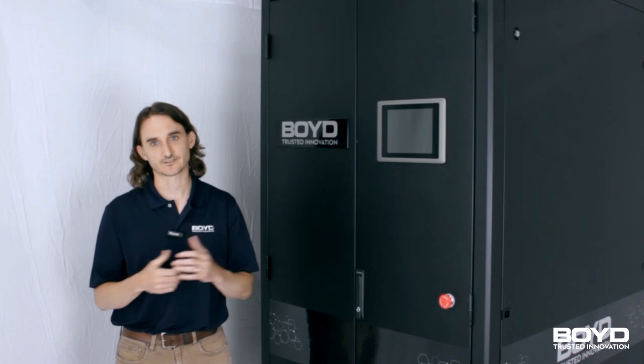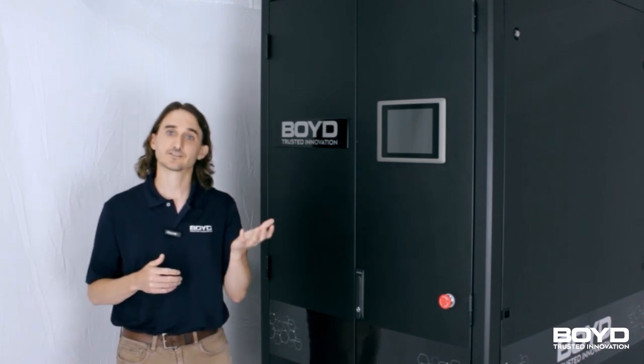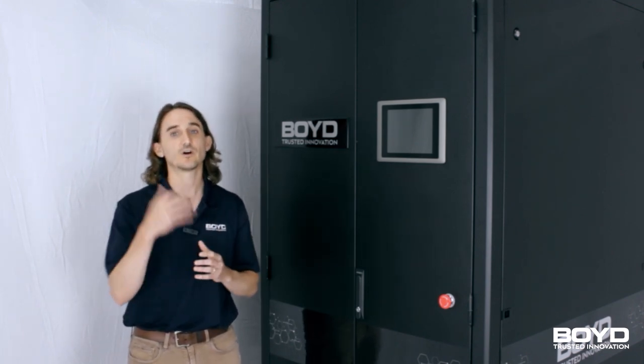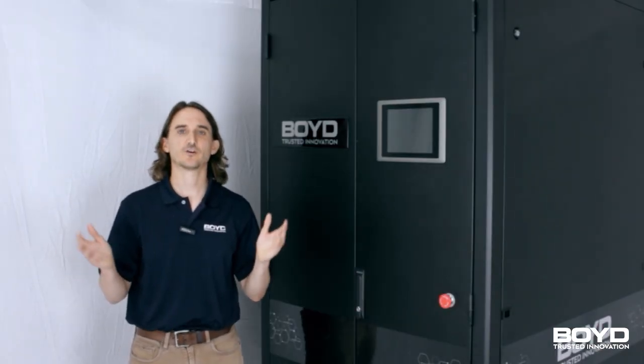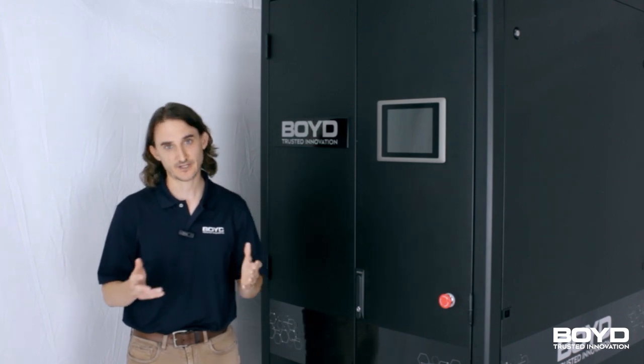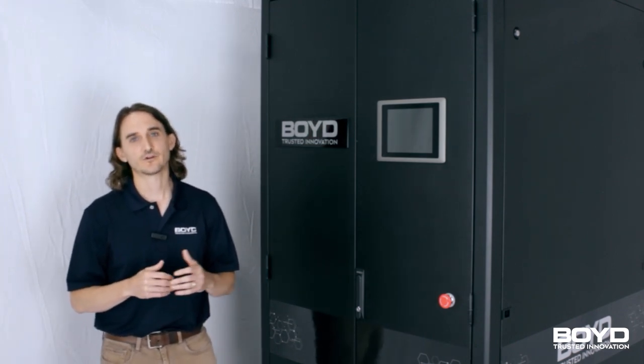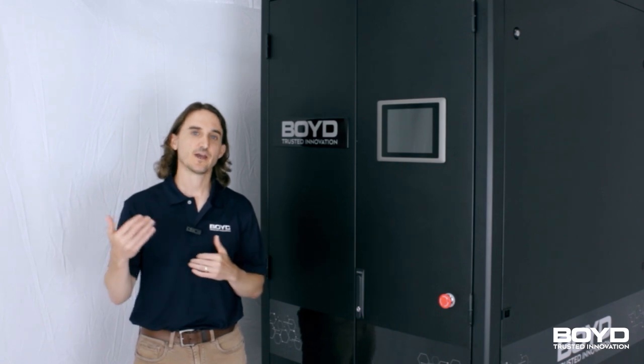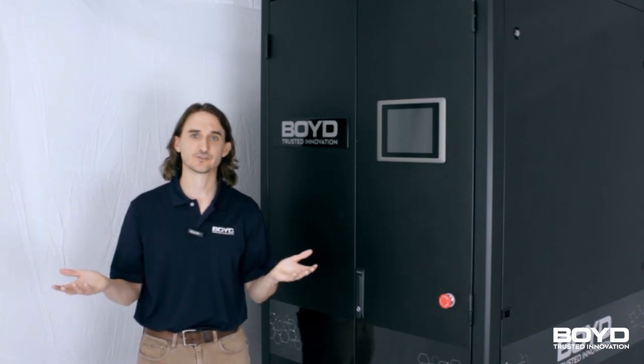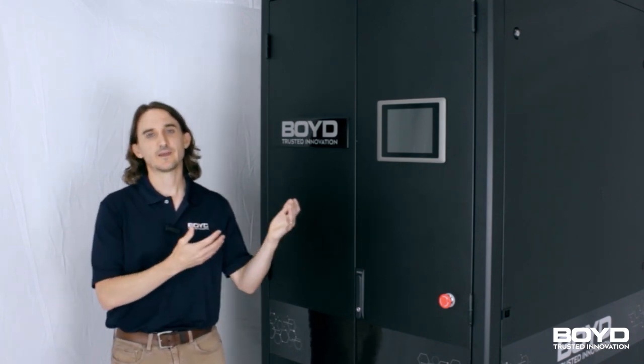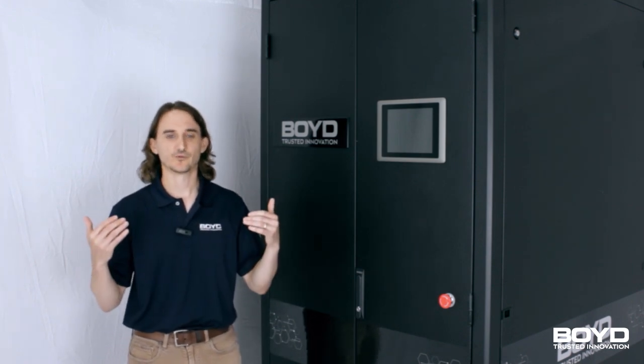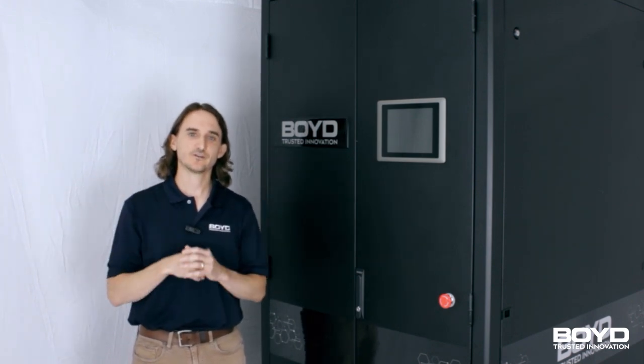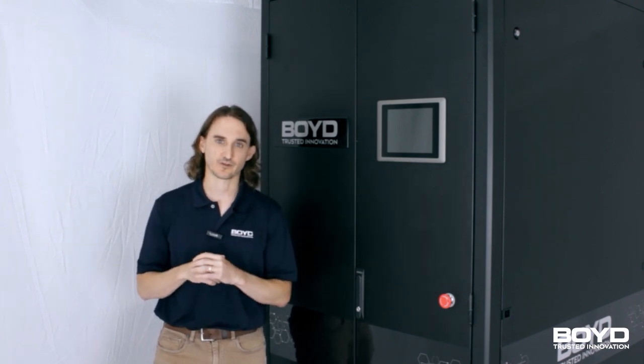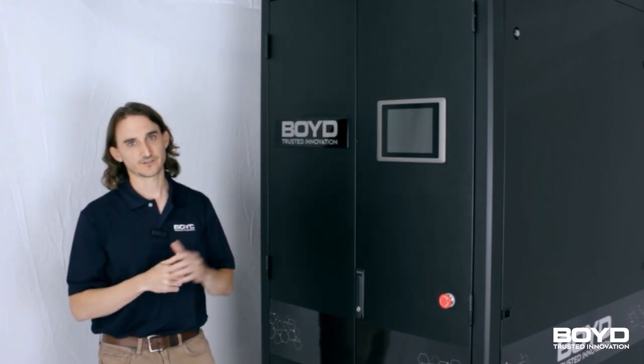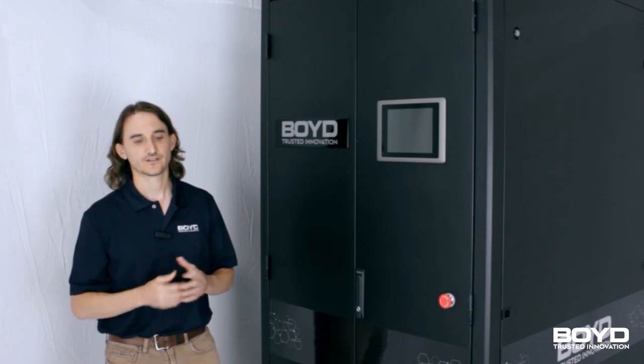We also have level sensors. Level sensors are in the secondary loop for the pump, as well as in the fill reservoir. This system also includes a fill reservoir and expansion tanks. The fill reservoir allows for makeup water if you have a server come in or out and you introduce air into the system. And the expansion tanks allow the system to fluctuate with temperature, as well as ensure a positive back pressure on the pumps. Back to the fill reservoir. It's a very convenient way to fill the system up.